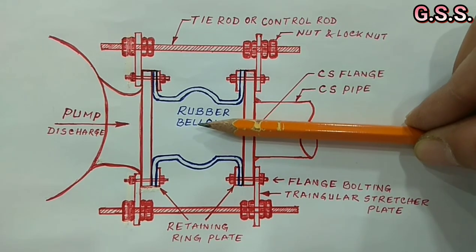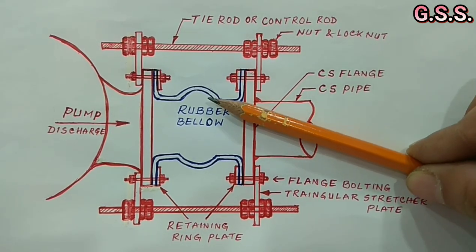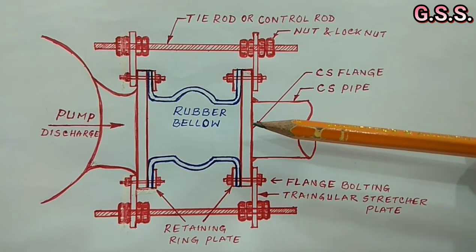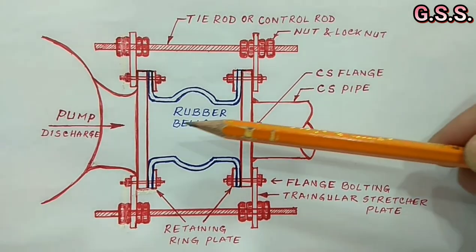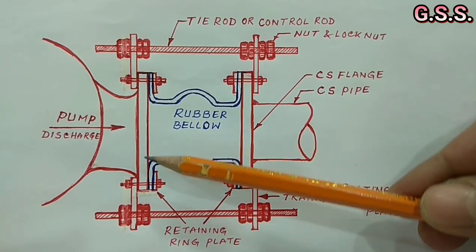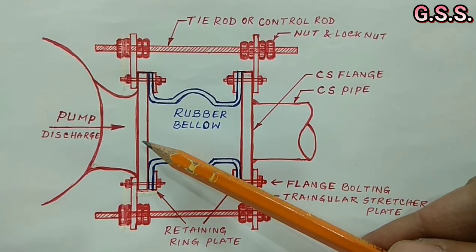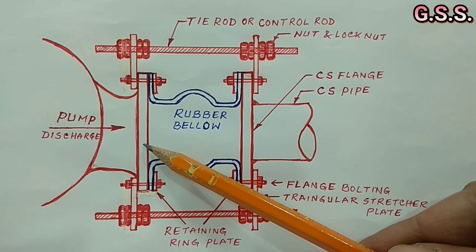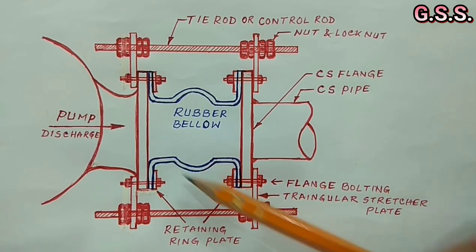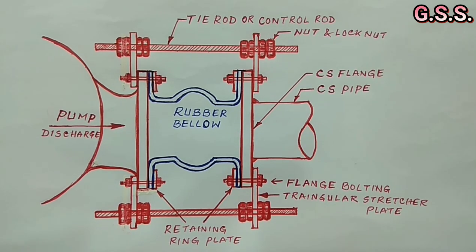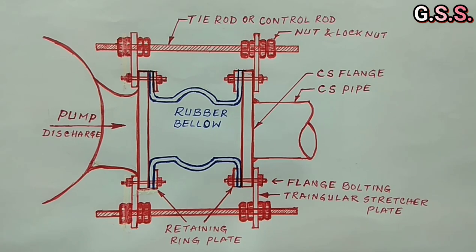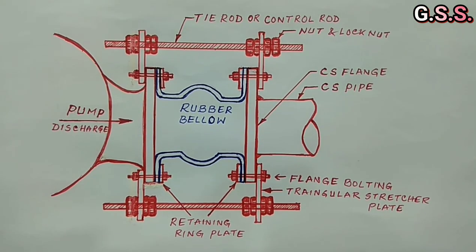With this minor misalignment, if we tight bolts of steel flange with pump nozzle, then stress will be developed on pump nozzle and pump nozzle gets loaded. If piping misalignment is more, huge stress will be developed in pump nozzle and pump nozzle or pump casing may crack.